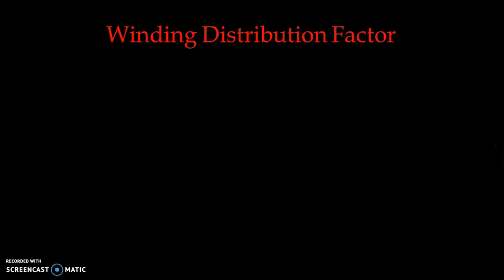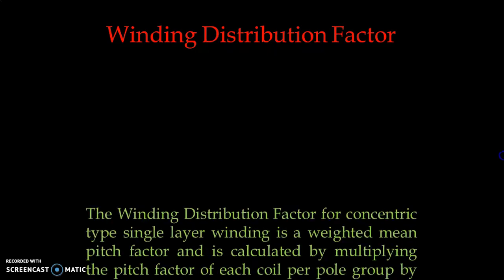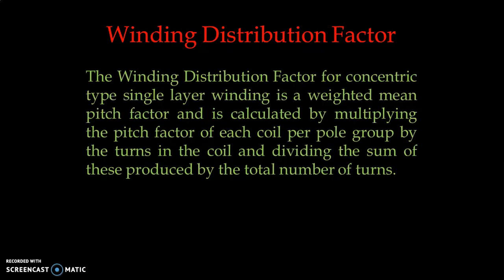Now let us consider the winding distribution factor and how to calculate it. This is the arrangement we have just considered for our nine slots and four different coils. The winding distribution factor for concentric type single layer winding is a weighted mean pitch factor. It is calculated by multiplying the pitch factor of each coil per pole group by the turns in the coil, and dividing the sum by the total number of turns. Let us see the equation form.